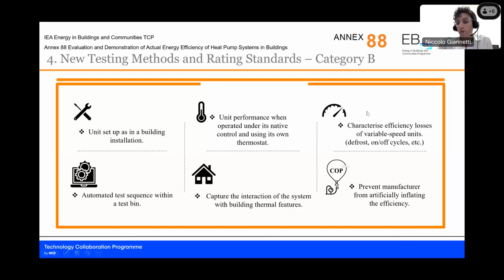During this test, we should be able to capture efficiency losses that come from the use of the inverter, so variable speed technology. This is usually a technology that provides the possibility to operate efficiently in a broad spectrum of conditions, so no fixed speed operation. But if the control is not properly designed, then we also encounter losses because of inconsistencies. Then, actually operating the system as installed, as it operates in a building, provides opportunities to automate the test.